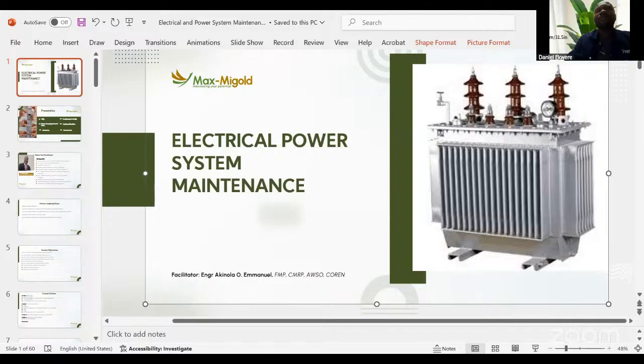It was not even up to 2 years before the genset started having problems. We didn't know what happened. But when we installed a system that monitors the load and power consumption, we started taking those records. We came to realize that at no point was the load in that estate up to 20% of the genset's capacity.